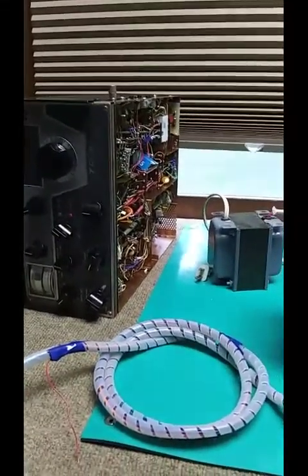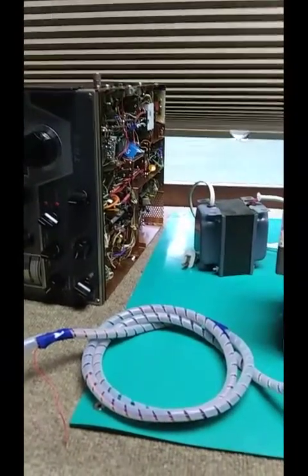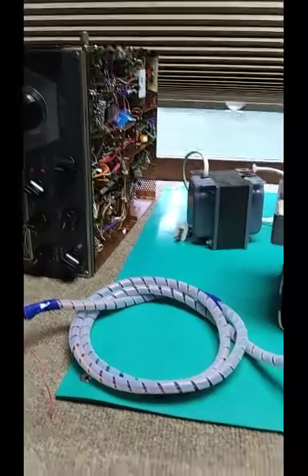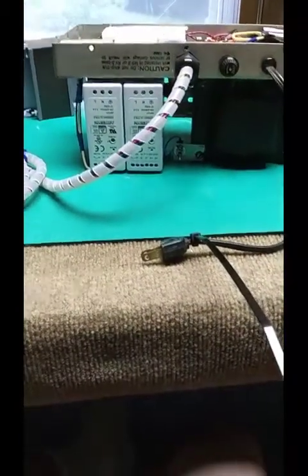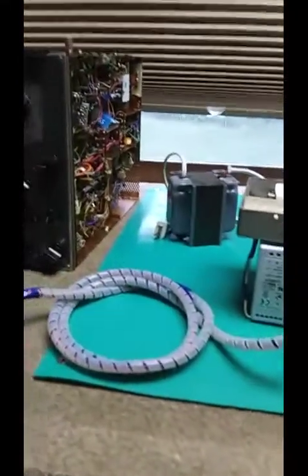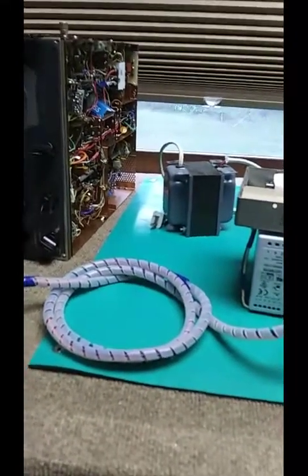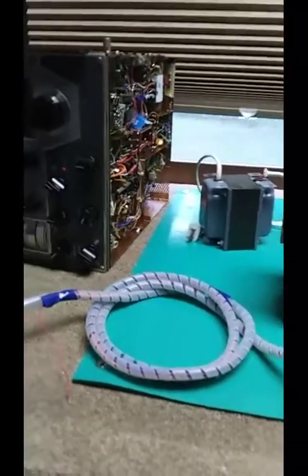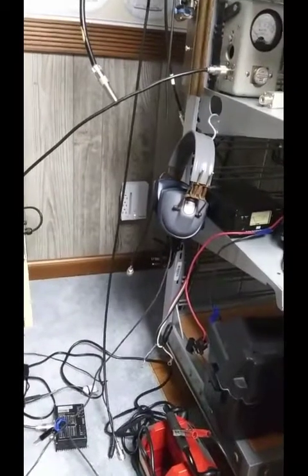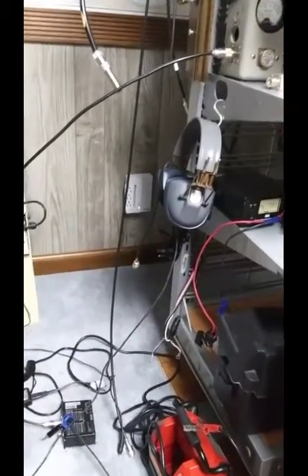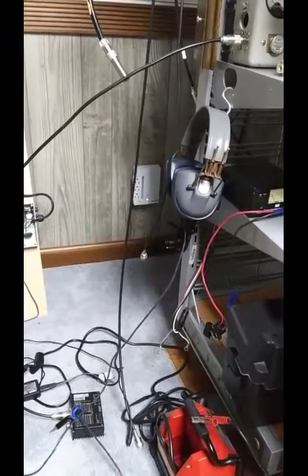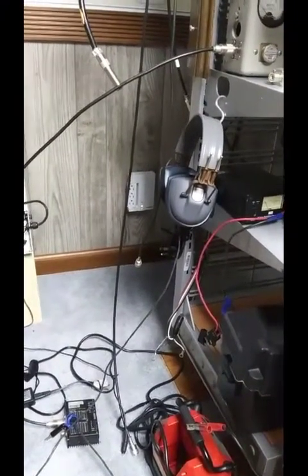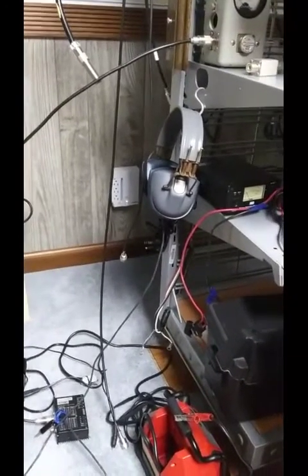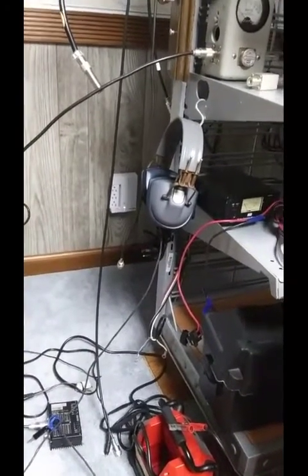So to deal with that came the practice in the 70s up to the 80s of having a 3rd wire cord with a ground prong and grounding the chassis such that if the neutral opens, the ground becomes a backup neutral. There is no such thing as ground on that outlet. That is not ground. It's not earth ground. It sure as 4-3 hockey sticks is not ground for a lightning transient. There's probably 250 feet of number 12 wire between that outlet and the ground rod, catty corner, other end of the house. That is not ground. It is a backup neutral.